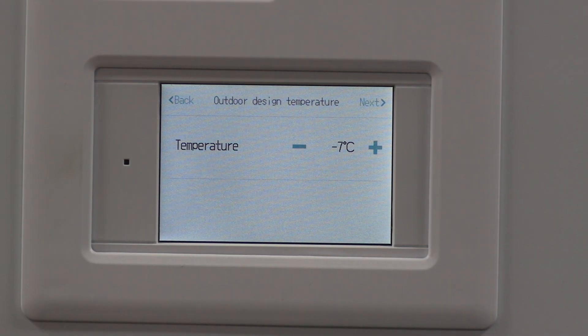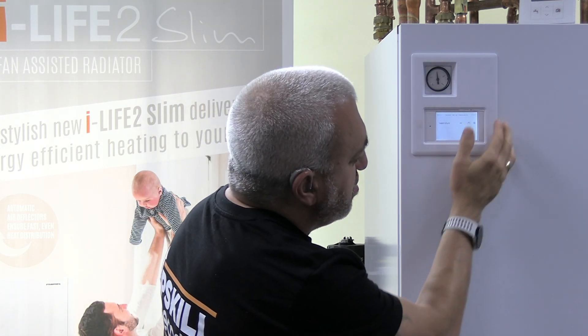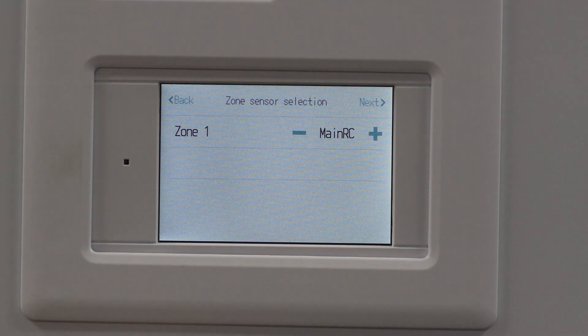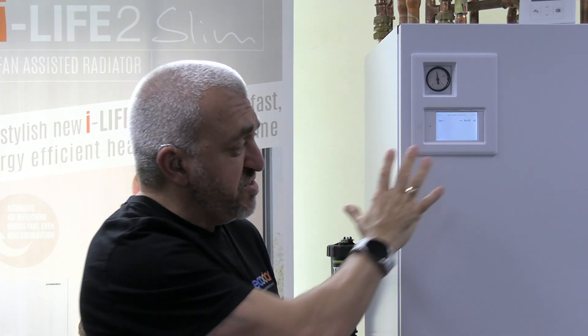The next option is the design ambient temperature. This is mainly based on where you are in the UK - whether you're in the south of England or the highlands of Scotland, there'll be a different design temperature. Most places in England would be around minus three. This setting adjusts some of the subtle background settings in the comp curve to meet the design temperature.